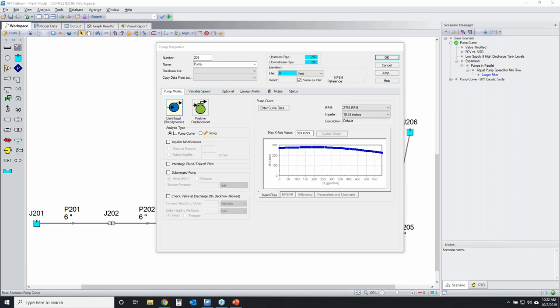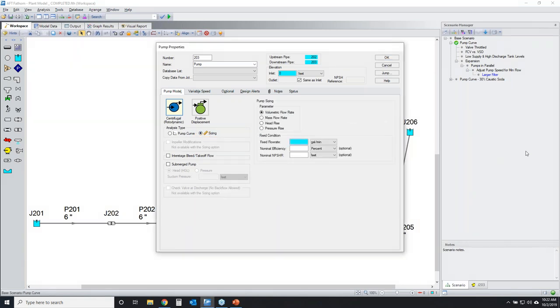Why does it do that? Well, the reason why is because when it changes it in the background to a pseudo sizing option, it can specify a fixed flow rate. And it's going to run your model over a whole range of flow rates where it's a fixed flow value. What it does is it calculates the required pump head that you need to generate the specified flow rate. That's how it plots out the system curve.